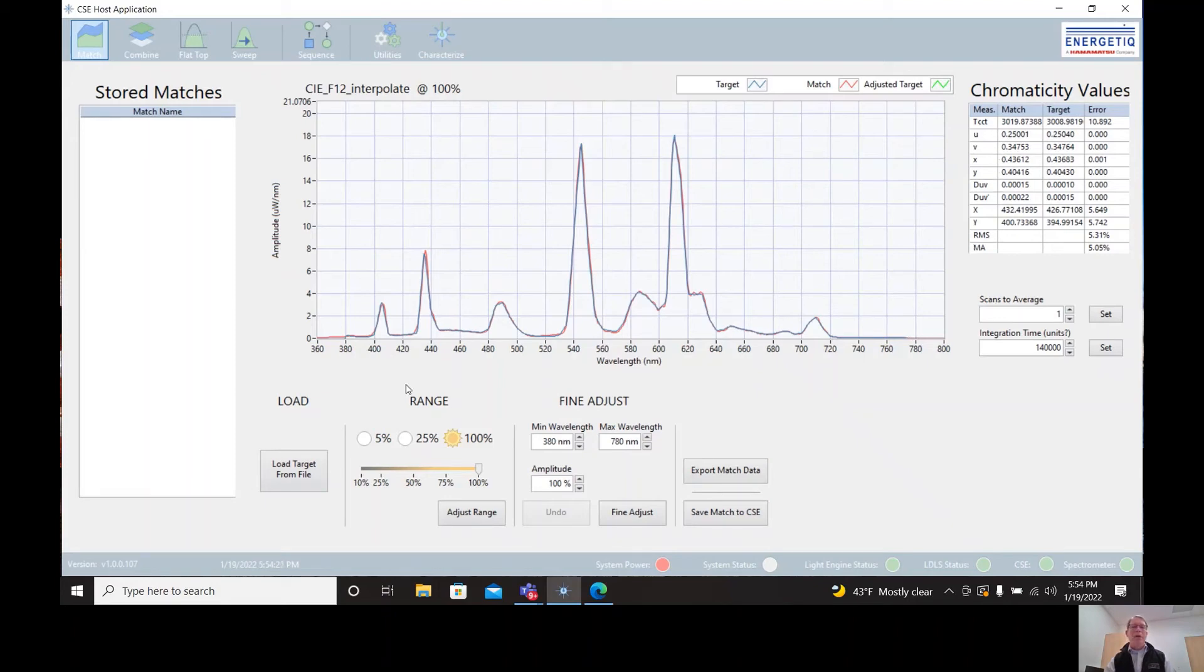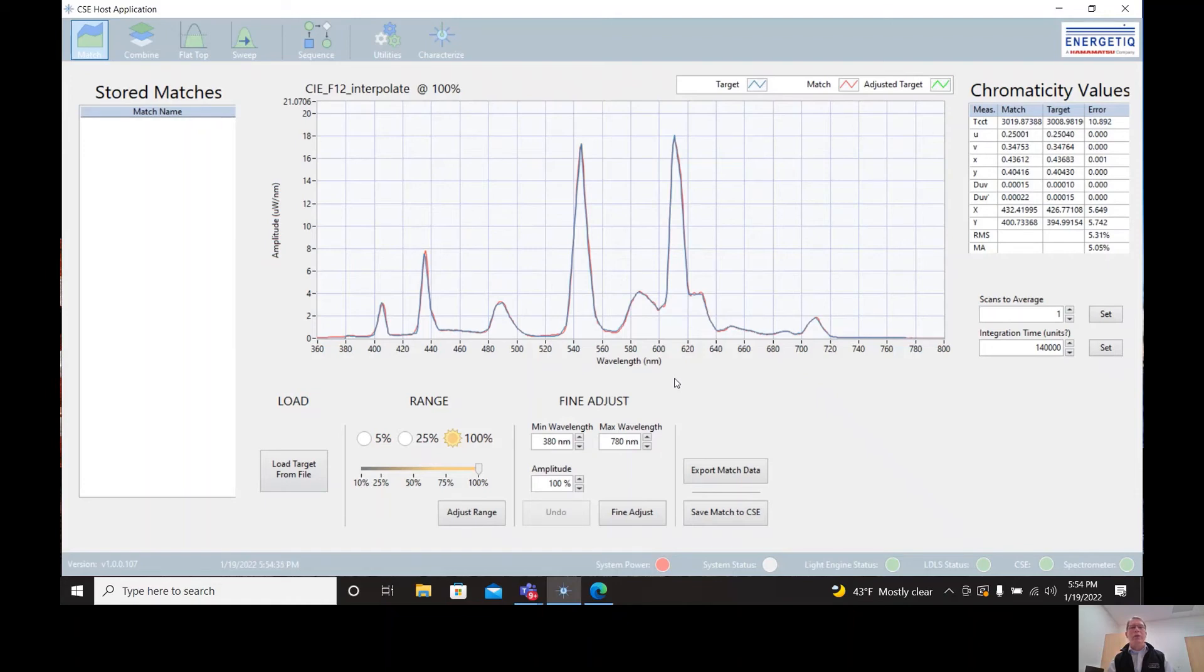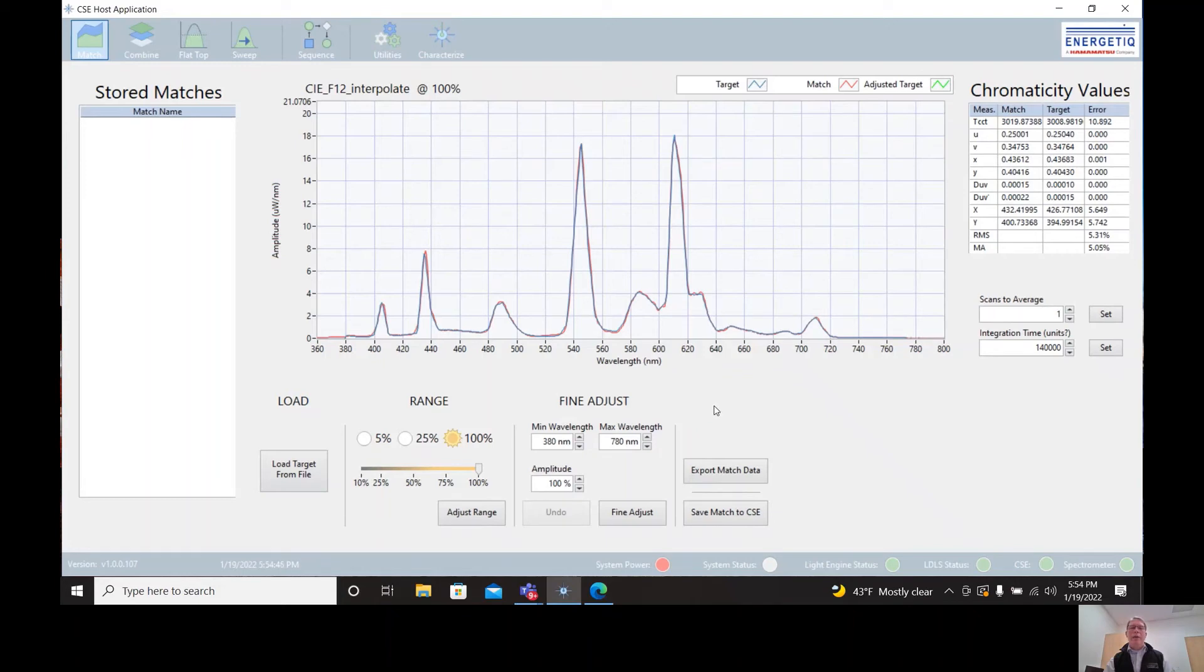And we can do any fine adjusting that we see fit. But the point here with the fluorescent source is that we can match these narrow peaks because of the high resolution of the CSE. The resolution is typically less than four and a half nanometers full width at half maximum. That's what allows us to match these peaks very accurately.